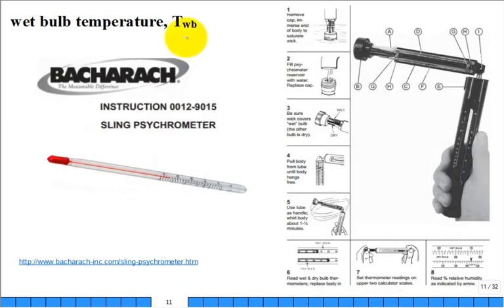Now, wet bulb, the easiest way is to describe it in the context of a sling psychrometer. Hey, there's that R, right? Sling psychrometer. It's a device that has two thermometers, one here, one there, with the sensing element, the bulb of the thermometer, down here and down here, and it swivels around this point. With your hand, you would twirl it and sling it around in the room that you're trying to make a measurement of. After twirling it for maybe 30 seconds, you would stop, grab it, and look at the thermometers.